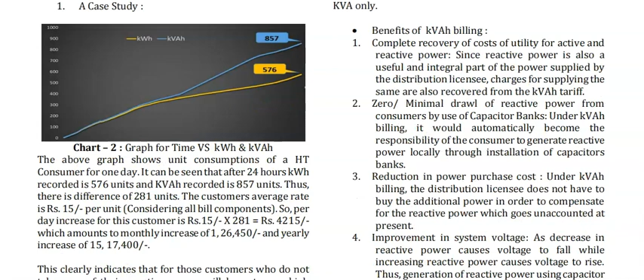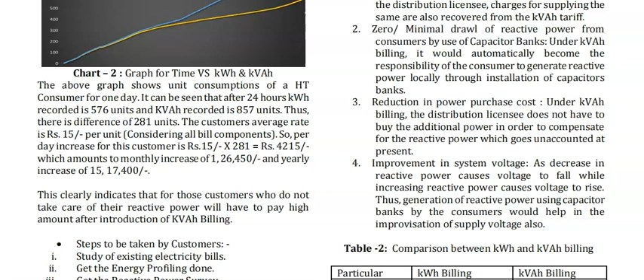So the per day increase for the consumer is 15 into 281, which is 4215. Monthly this increases to 1,26,450, and yearly it increases to 15,17,400. This clearly indicates that customers who don't take care of their reactive power will have to pay a higher amount after the introduction of kVAh billing. If anyone does not take care of their reactive power, they have to pay more. If anyone takes care of their reactive power, they have to pay less.